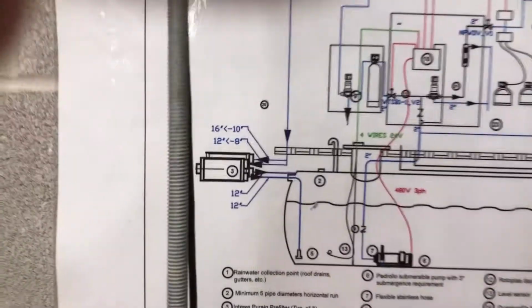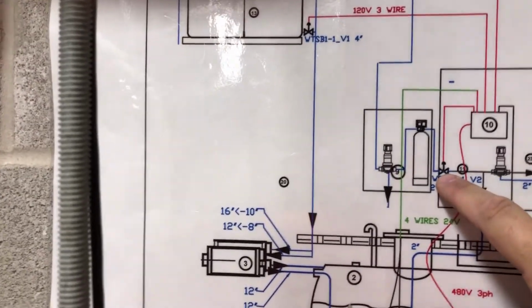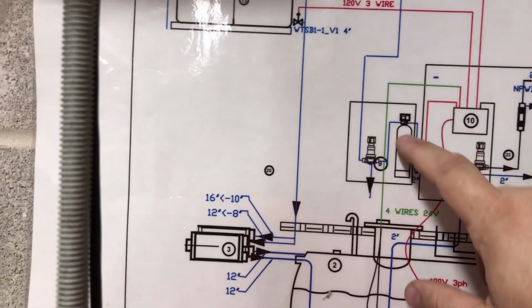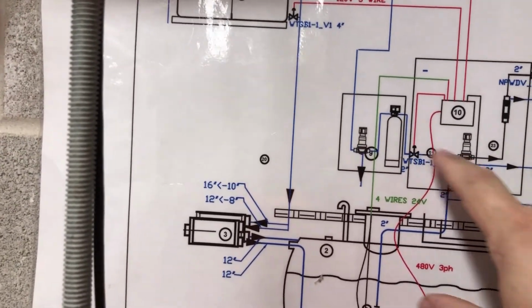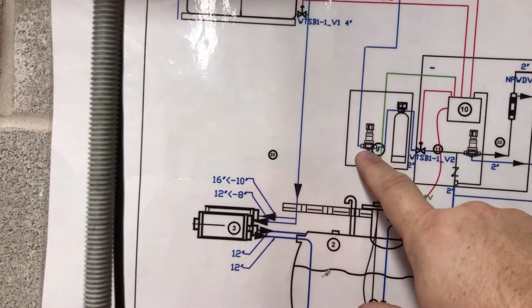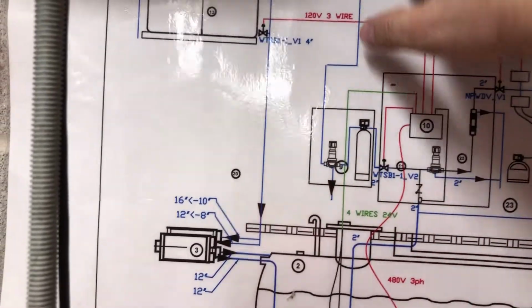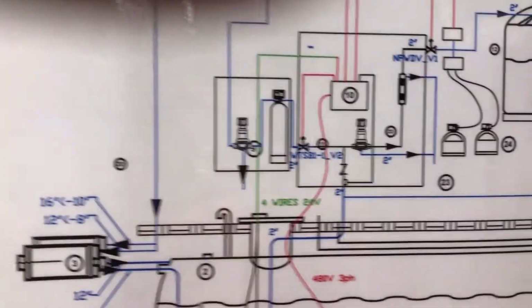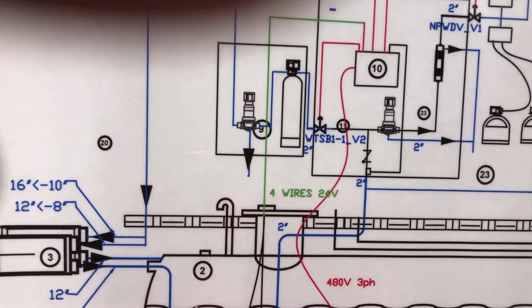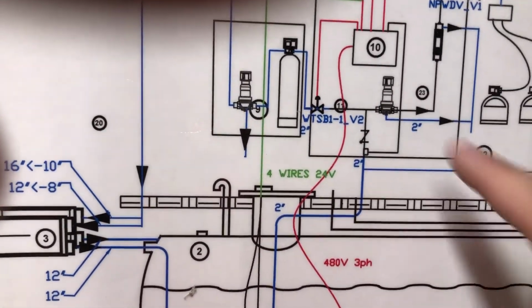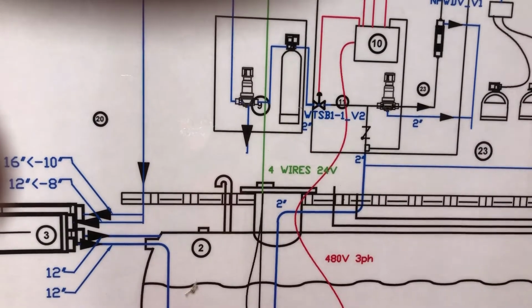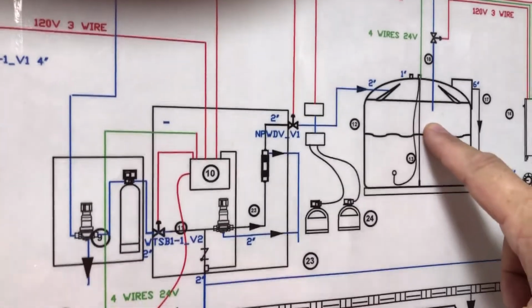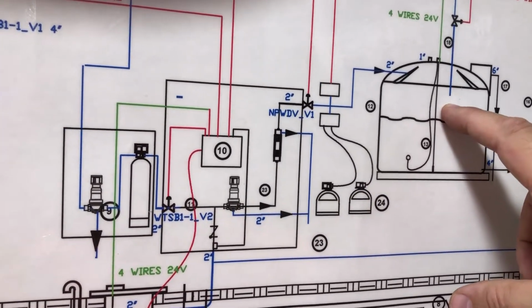That water, before it comes to us, here's the valve I was just pointing at in person. Before it gets to this treatment skid, it goes through a water softener and another sediment filter. So that's city reclaimed water getting further treatment before it goes through the UV. The water then flows up to the day tanks that are outside.